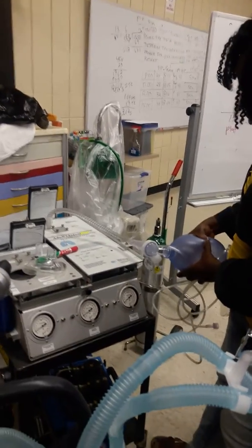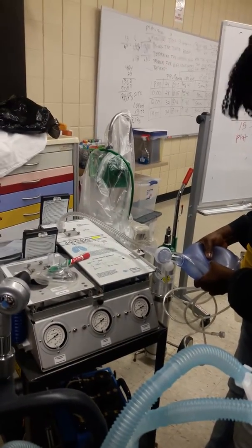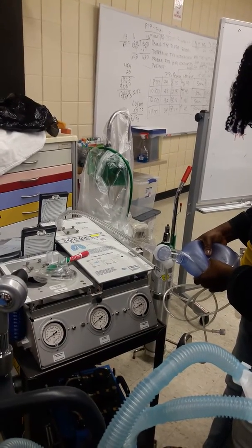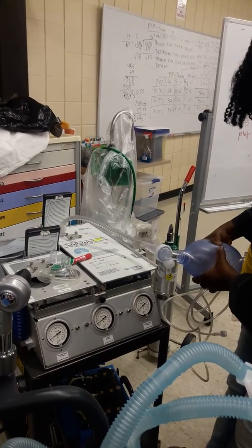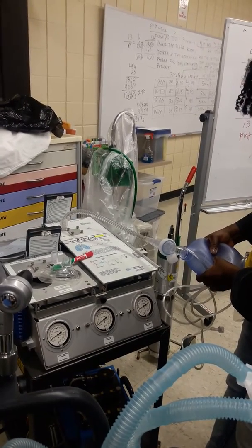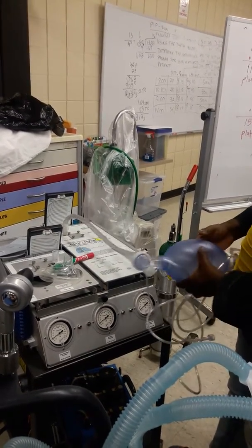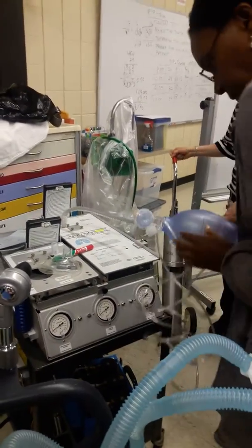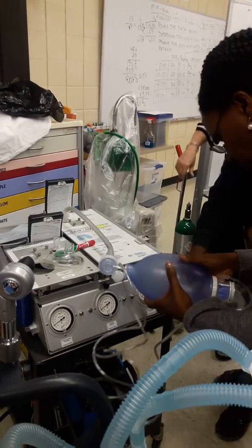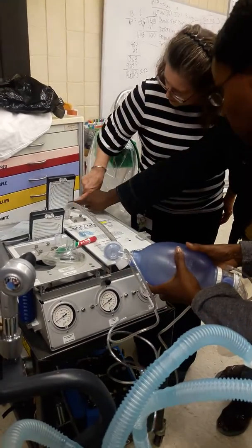So go ahead and bag it to 500. And then hold it for a second. You'll see your plateau is 5. So everybody, give it a couple of squeezes so you know what it feels like. Pause is plateau. This is where you can see your plateau.